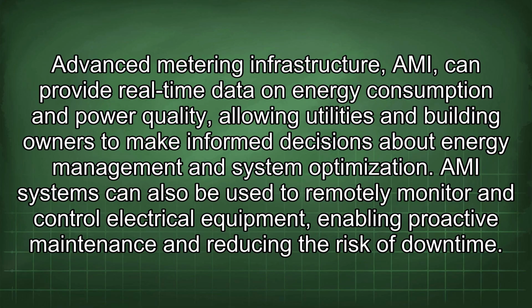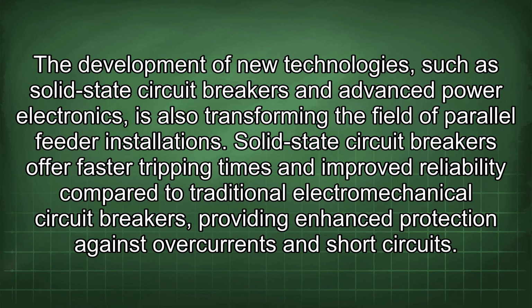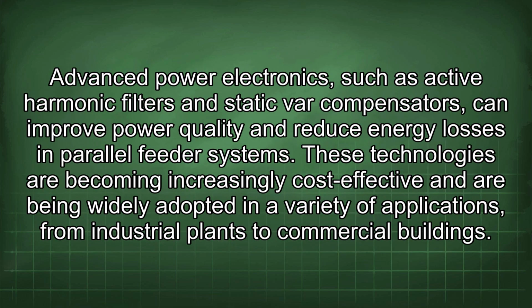AMI systems can also be used to remotely monitor and control electrical equipment, enabling proactive maintenance and reducing the risk of downtime. The development of new technologies, such as solid-state circuit breakers and advanced power electronics, is also transforming the field of parallel feeder installations. Solid-state circuit breakers offer faster tripping times and improved reliability compared to traditional electromechanical circuit breakers, providing enhanced protection against overcurrents and short circuits. Advanced power electronics, such as active harmonic filters and static VAR compensators, can improve power quality and reduce energy losses in parallel feeder systems.